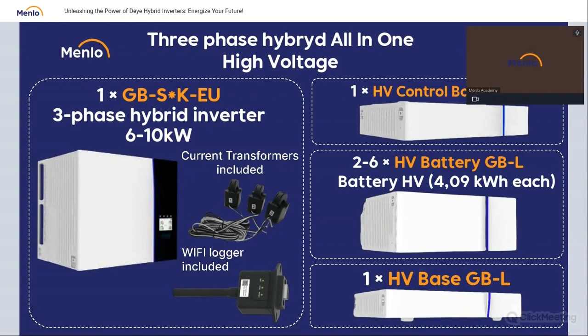Here it says that the Deye hybrid inverter has 100% unbalanced output in each phase, with max output up to 50% of rated power. All hybrids from Deye have phase unbalance. They are asymmetric, and they allow you, without time limitation, to produce or send to the grid, on each particular phase, up to 50% of its overall power, and up to, I guess, 30 seconds, even 100% of the inverter. So when you have a 10 kilowatt inverter, for up to 30 seconds you can put 10 kilowatts in one single phase, and without time limitation, 5 kilowatts for each phase, no matter which one you want.